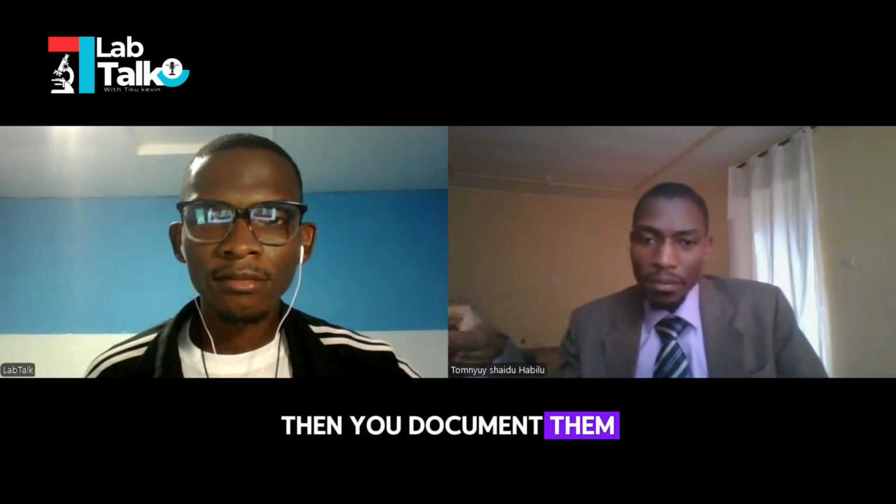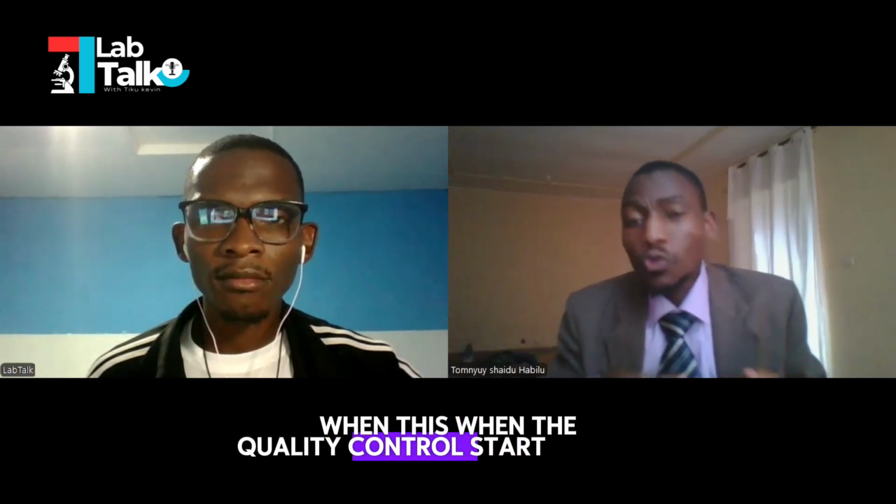You start observing a shift and a trend because normally with quality control, when you run the quality control, you document them, and there is a graph. They call it the Levey-Jennings chart. Yes, where you run quality control and then you document them on this chart. When the quality control starts shifting, it starts giving you an idea that here there is a possible systemic error, here there is a possible random error. So it gives you the idea.